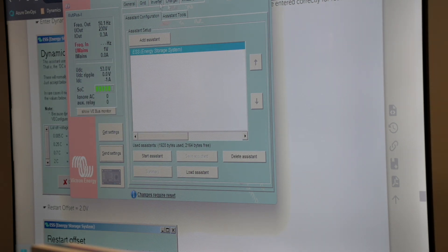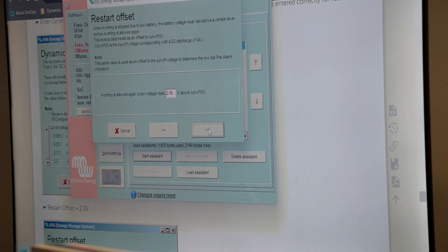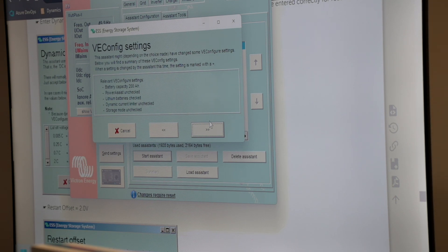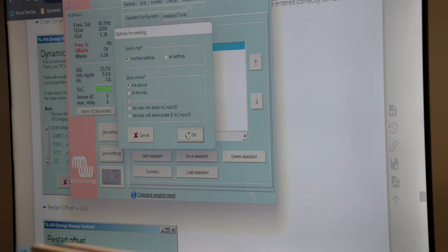So all these settings you can adapt and then go and say all devices, and just add your assistant to this device. I'm just going to set my PV power here — it won't allow you to have more PV power than the system. Let's go with an 8 kilowatt inverter and 9 kilowatts PV just to be safe. It's going to give us an overview of the VEConfig settings. We're happy with that. Now we can go and say send settings to this device only.